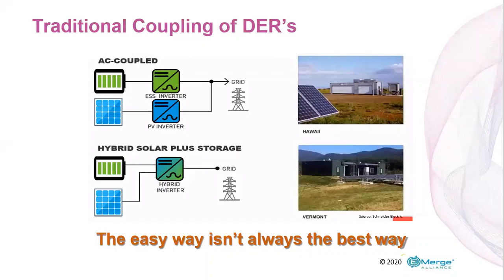AC coupling was really centered around the early implementation of solar connections. If we go back at least 10 years or more, simply connecting solar panels through a PV inverter of some type connected directly to the grid, so it's grid tied, and essentially you're putting the power on the grid, which could come back into the local premise, but also was just common with the other power on the grid. So whether it was whole or part of the local load, it really was connected to the grid and not directly connected to the local loads.